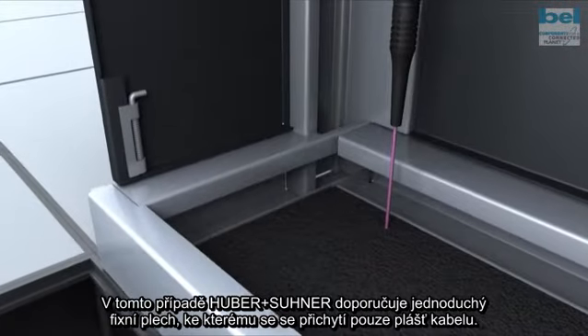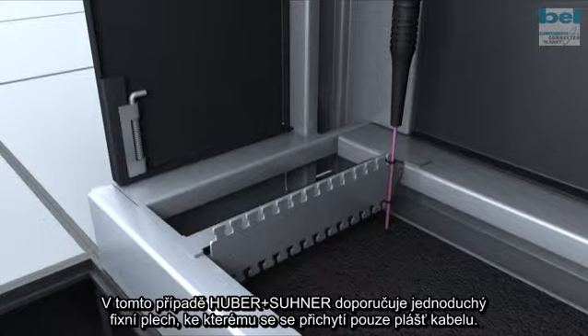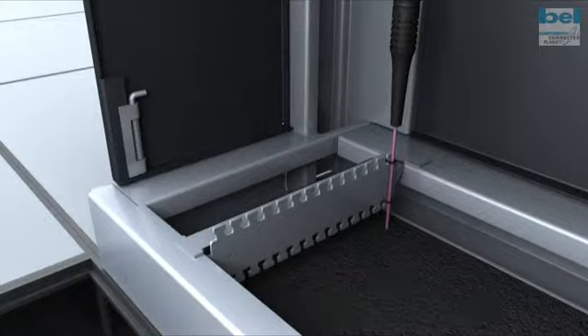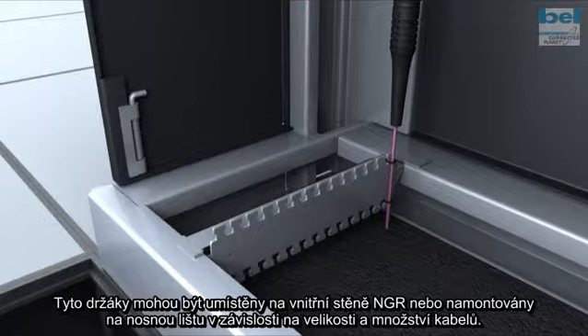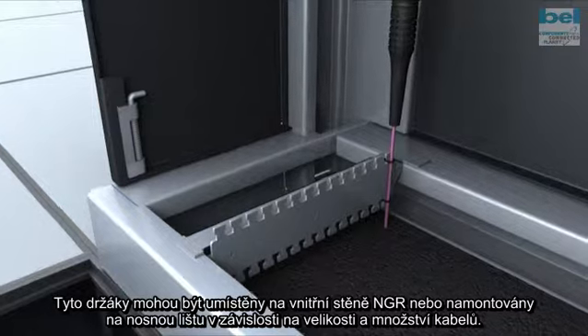Cables which are pre-connectorized, such as MPO cable systems, require considerably less protection than loose tube cables, and in this case, Huber+Suhner recommend a simple tie-off plate where only the outer jacket of the cable is fixed to the rack. These tie-off plates can be placed directly against the inner wall of the NGR or mounted on a support rail, depending on the size and the quantity of the cables.